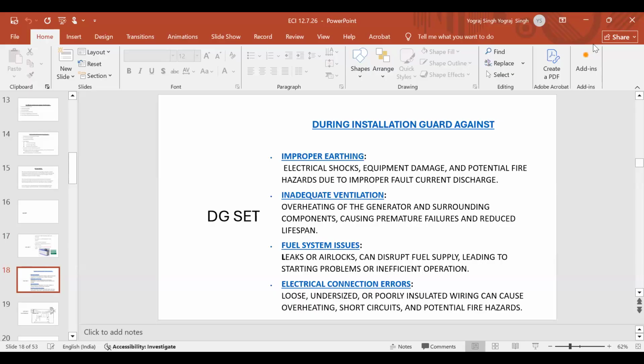Now, when the new DG set comes, you do the load testing. I hope everybody is aware of the kW and kVA considerations. When you order it, you ask your vendor to bring the load. It is normally a resistive load, where they use a water load. So you may say my DG set is 500 kVA, so I will test it with a load of 500 kilowatt because my power factor is 1.